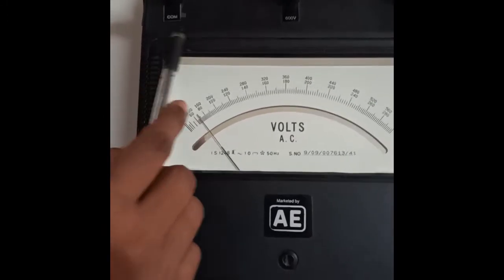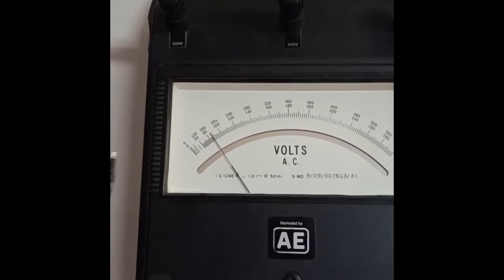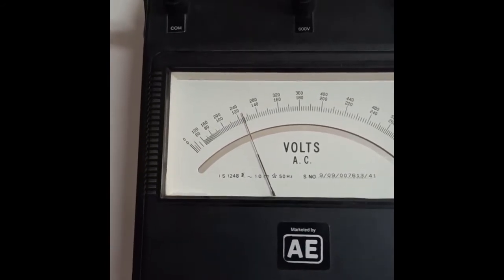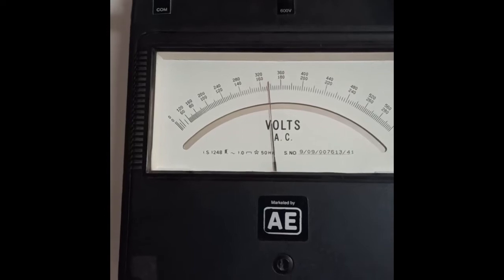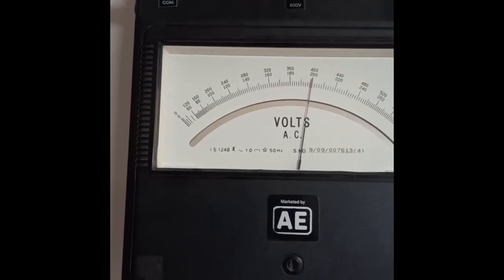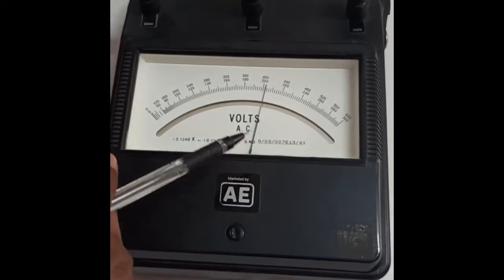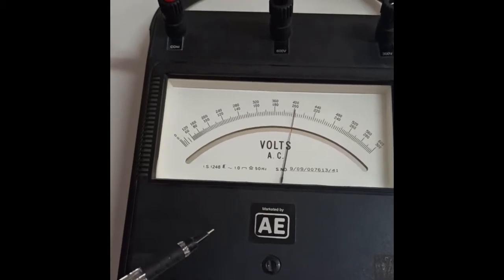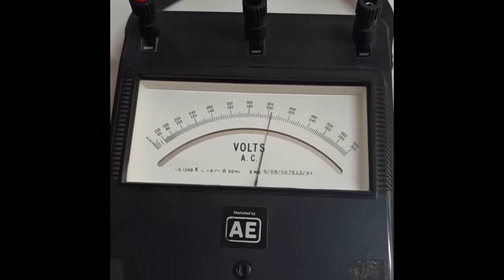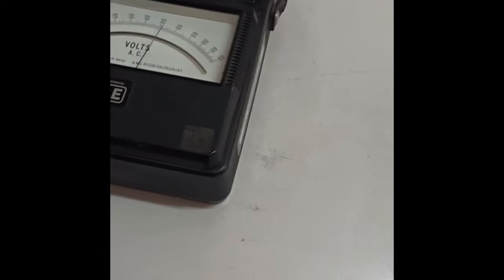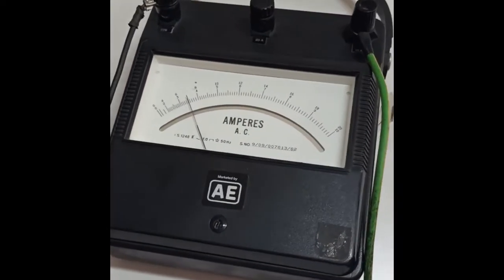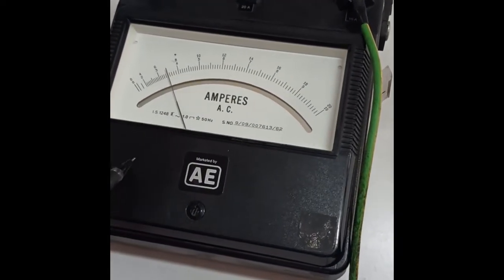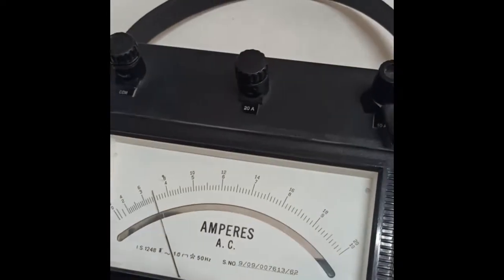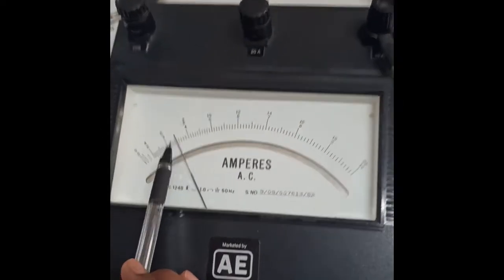We are using the scale 0 to 600 volts, so we have to check for the upper scale reading. Let us adjust the voltage of the machine to 400 volts. You have to ensure that the voltage across the voltmeter is 400 volts. Now under this condition you have to note down the no load readings. Under no load condition, the current here, lower scale reading, is around 3.5.